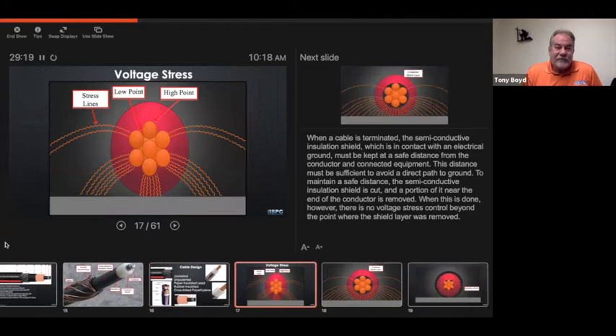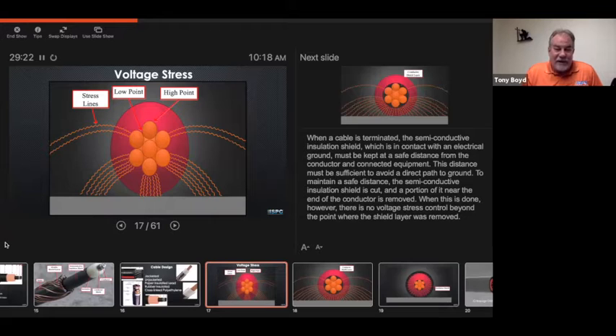All right, this is what we're all waiting for: the voltage stress when the cable is terminated. The semiconductor insulation shield, which is in contact with electric ground, must be kept at a safe distance from the conductor and connected equipment. That distance must be sufficient to avoid a direct path to ground. So to maintain a safe distance, the semiconductor insulation shield is cut and a portion of it near the end of the conductor is removed. When that's done, however, there's no voltage stress beyond what we're talking about. So basically, you can see right in here a low point and a high point.